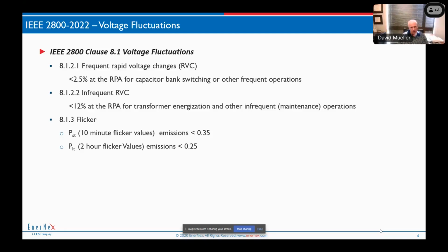We do transformer energization studies, and I think most of the time the short circuit ratio is enough that we don't hit that point. Transformer energization, by the way, is what we call a point on wave phenomenon, which means that depending on when the breaker closes, depending on the remnant flux stored in the transformer, you might get a different answer for every simulation. We typically, when we do the studies, do 100 statistical shots at different timings to see what's the worst.